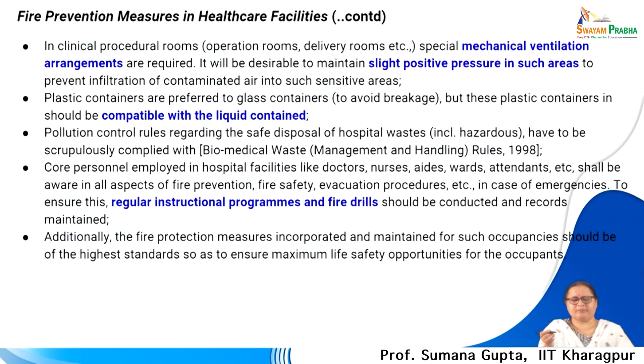NBC also has minimum requirements for firefighting installations in hospitals. You can refer to the National Building Code for design, which specifies the water requirement, both static and overhead, the pump requirement, its capacity, and the pressure requirement. Usually it is 2 bar pressure at the rooftop and 3.5 bar at the booster pump level. These are all worked out and given in the NBC, so I have not crowded the slides with that data.